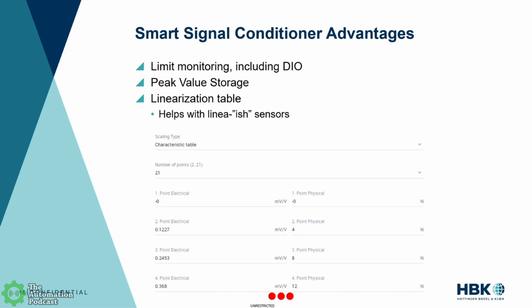Yeah, that can be super painful to do in the PLC and very memory intensive in the PLC, and something I could see if you have a sensor that you can't replace and it's not very linear and you're struggling with it, this could be a reason. That could be a reason alone just for getting one of these to do that, because again, doing the PLC code, unless you've done a lot of testing and created your own add-on instruction to do it, or function blocks to do it, it's painful. It's painful. This just makes it go away.